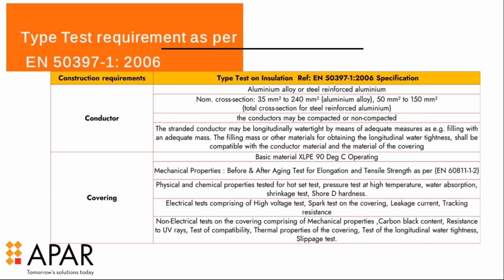The stranded conductor may be longitudinally watertight, as I told you, by means of adequate mass added to it. That is the semiconducting gels, which are used during the stranding of the conductor to make it a foolproof watertight conductor. Then they talk about the covering, which is basically the XLPE covering, which can withstand up to 90 degrees centigrade operating. And mechanical properties, before and after ageing test, elongation test, tensile strength test as per EN 60811 part 1-2. Then physical and chemical properties tested for the hot set test, pressure test, high temperature test, then water absorption test, then shrinkage test, and the shore hardness.